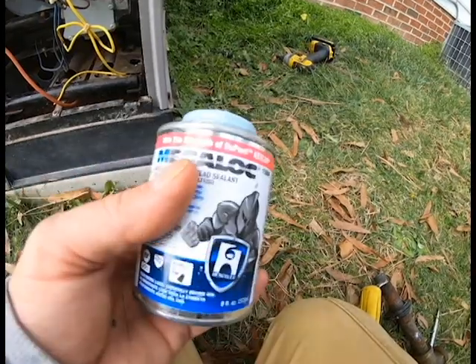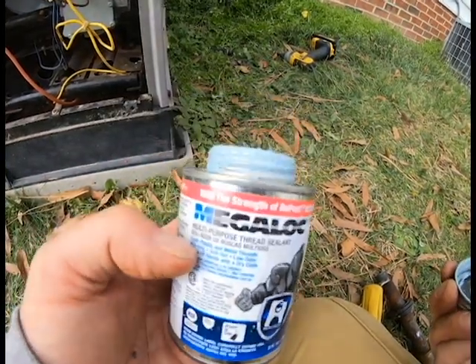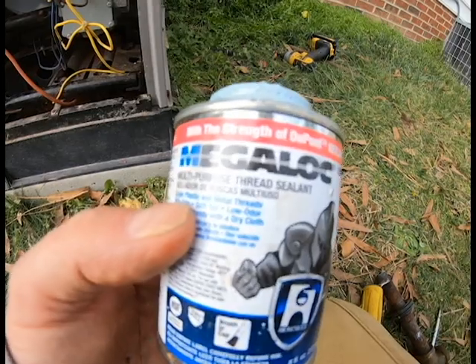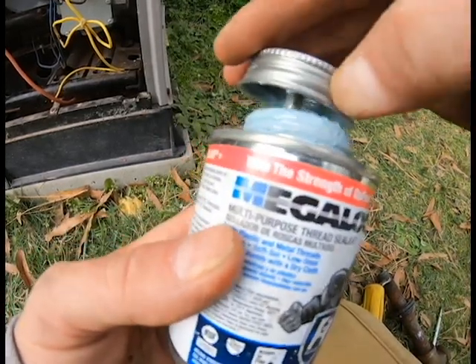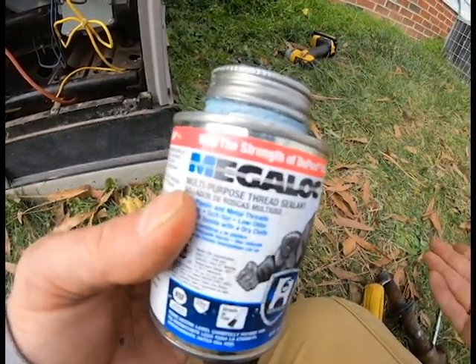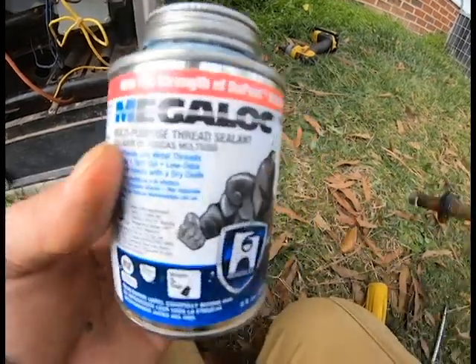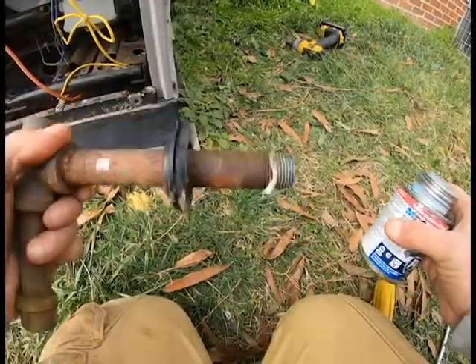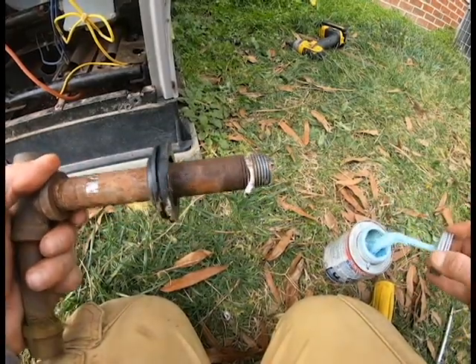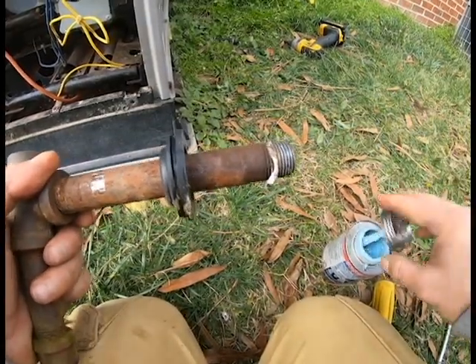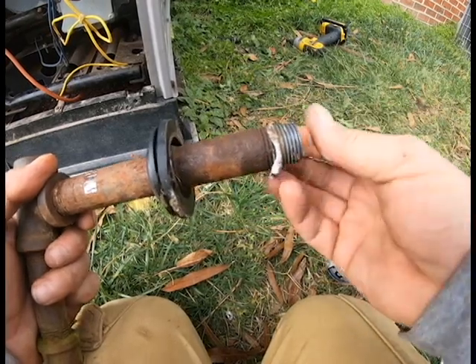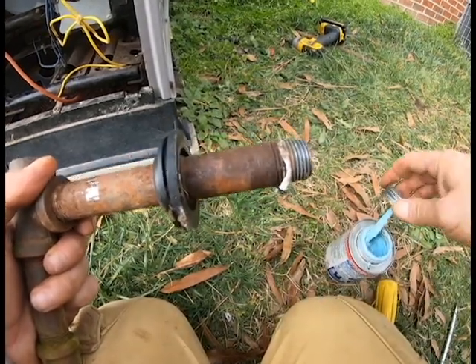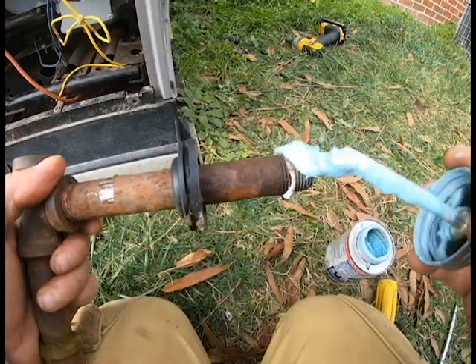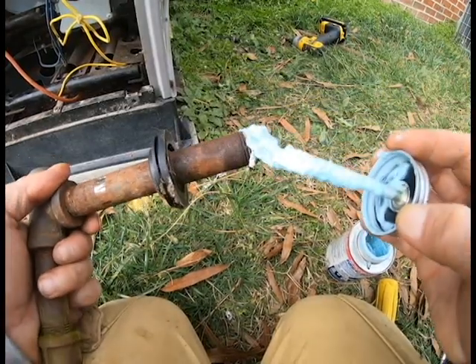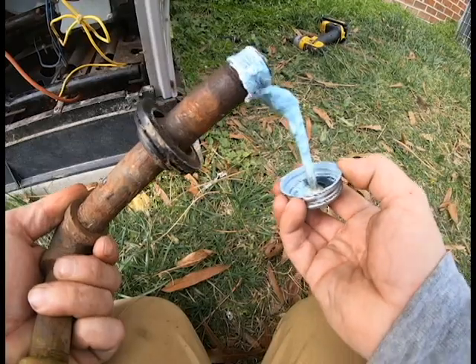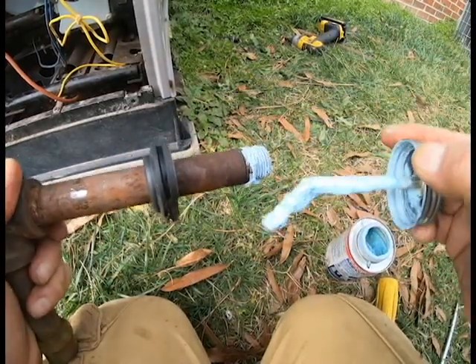All right guys, whenever you're putting a gas line back together, you want to make sure the threads are sealed. This is a thread sealant, or otherwise called pipe dope. We take that and put it on the threads of our gas line, and that assures that when you tighten it back up, it'll seal the threads and we won't have any gas leaks. So we're just going to put this on like so.